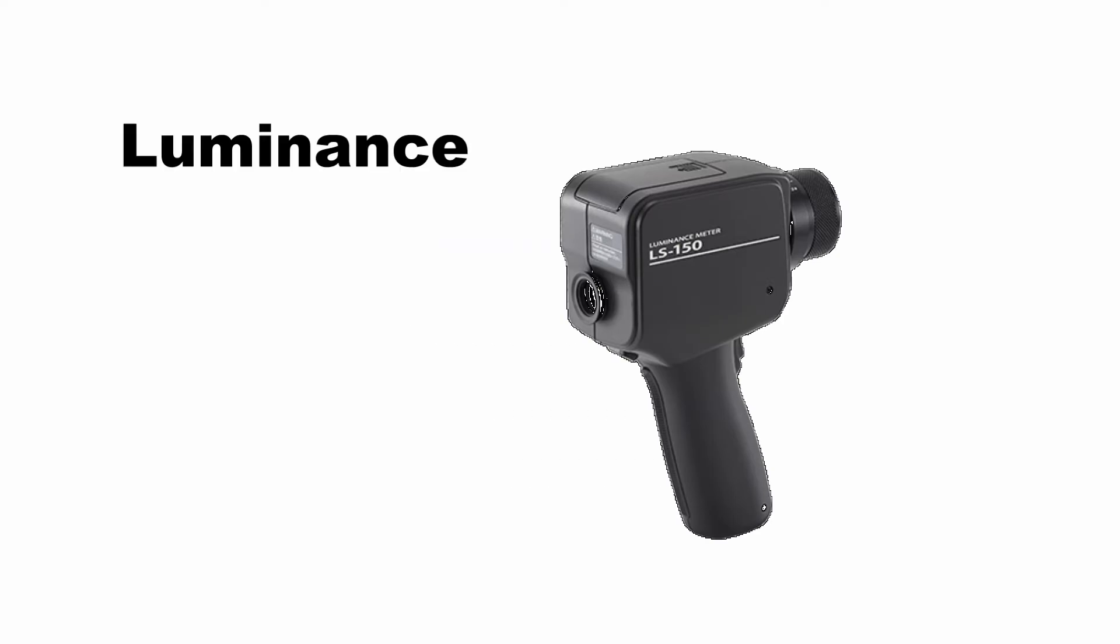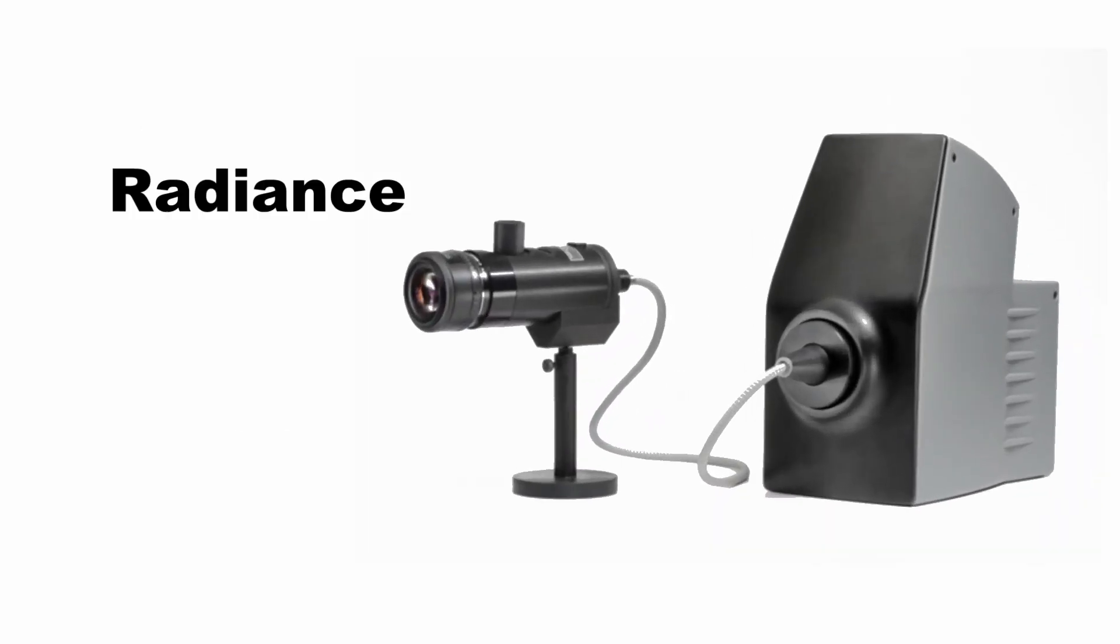Luminance is measured with a luminance meter that is calibrated to the photopic curve. Radiance is normally measured with a spectral radiometer, which gives the radiance as a function of wavelength. The final measurement is the integral of the spectral measurements.